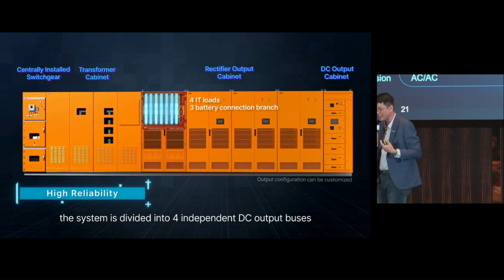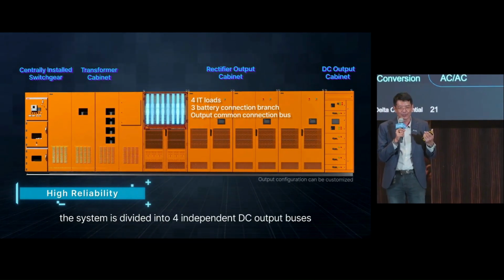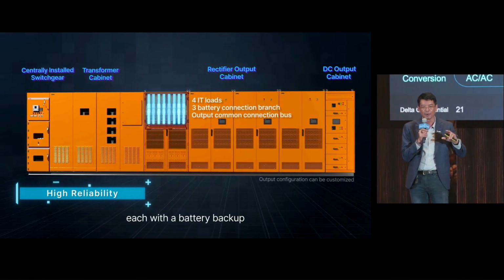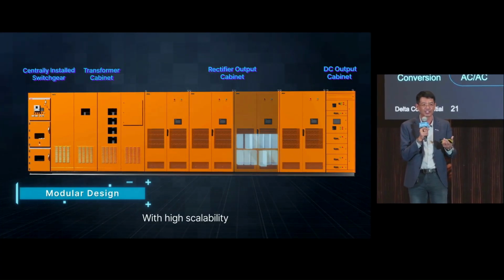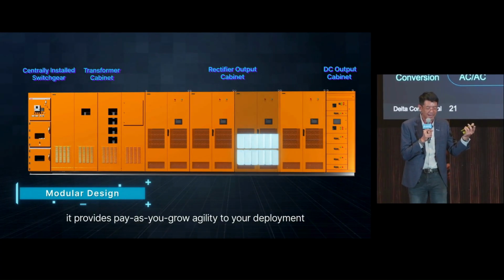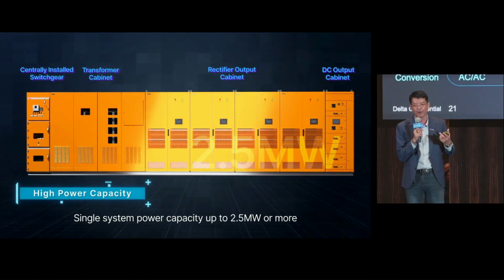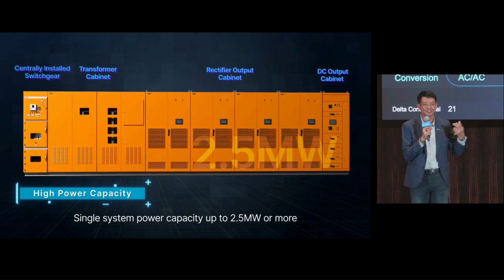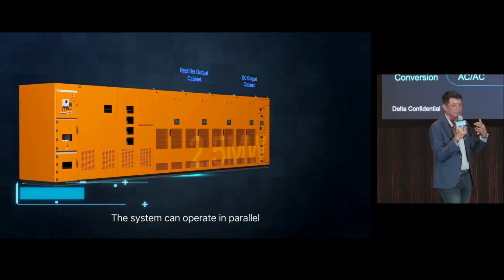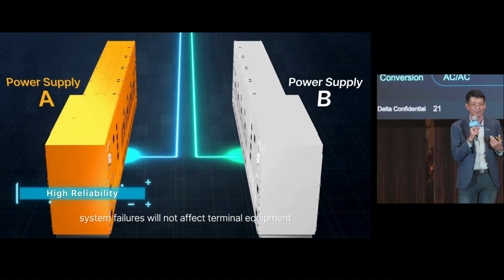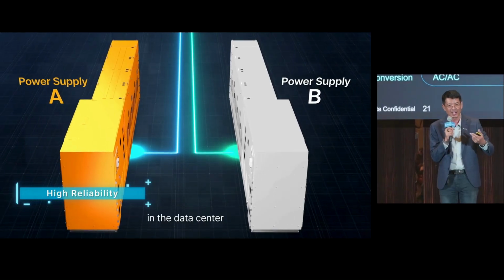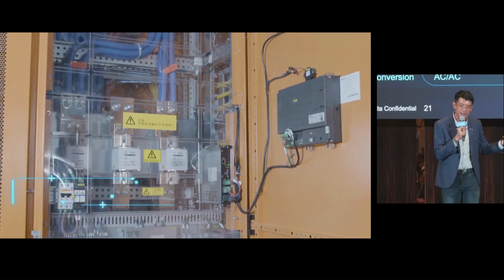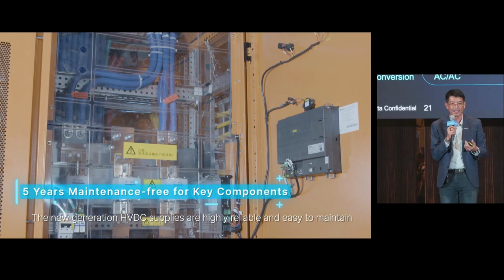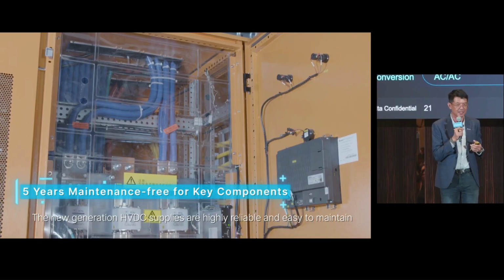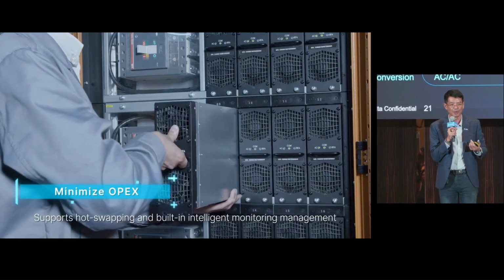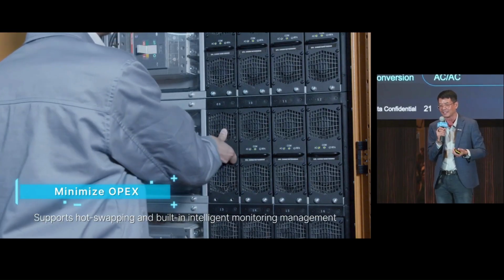So that's why I think the Panama solution is still the most practical way today, because with plus 400 and minus 400, we can keep using the existing power distribution system, the breakers, and those kinds of things, and we can implement high impedance ground fault detection, which meets IT system requirements and IEC standards.